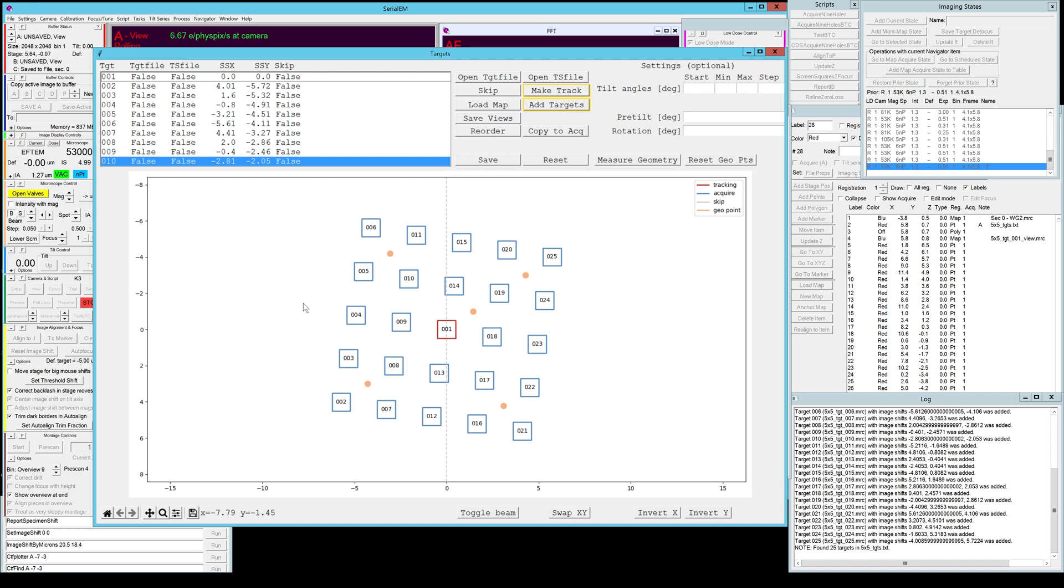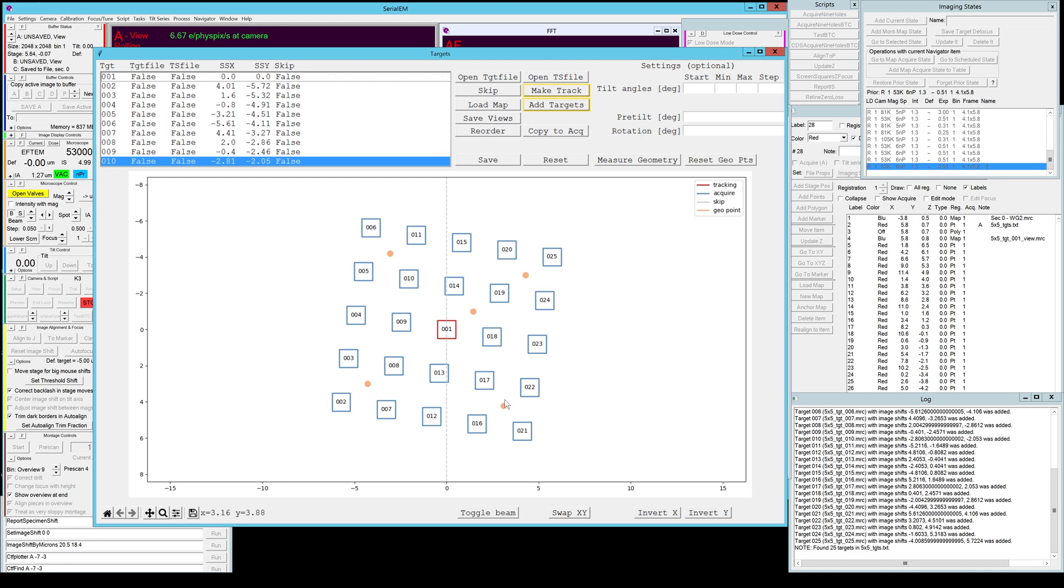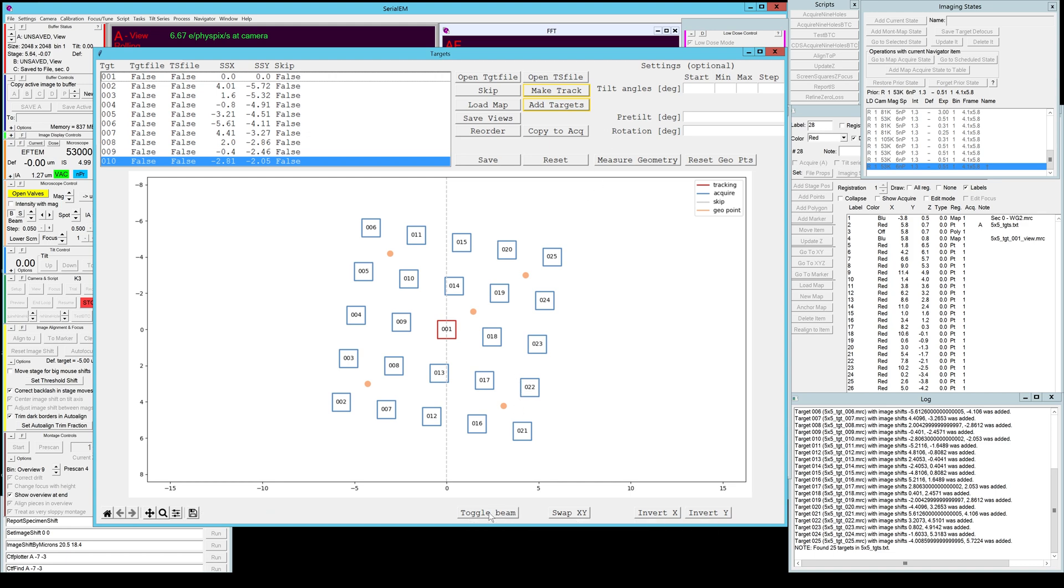This is especially useful for really large patterns because of course your support film is very rarely absolutely flat. So you can treat it as kind of a tilted plane similar to a lamella with a pre tilt and rotation. You can measure by measuring the focus at these different predetermined points and then fitting a plane towards the focus measured and calculating pre tilt and rotation.